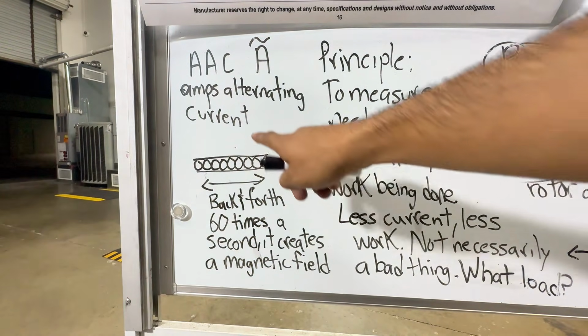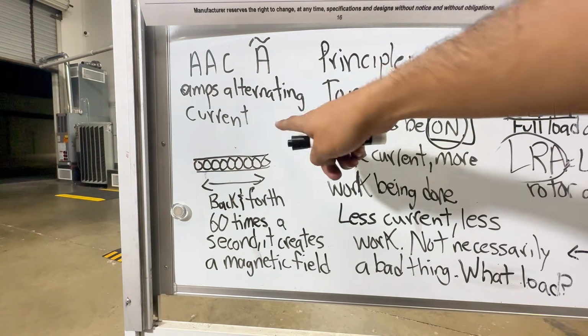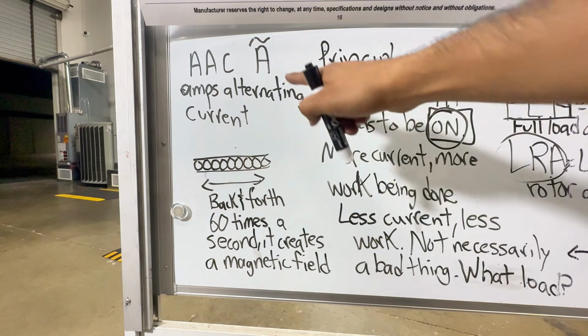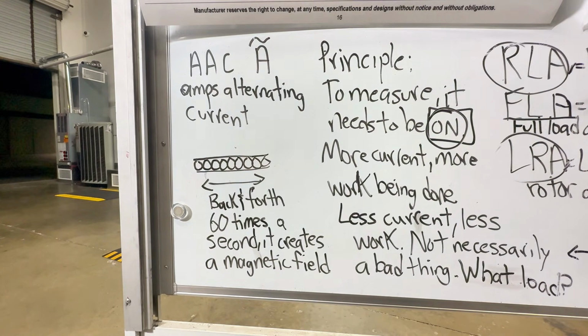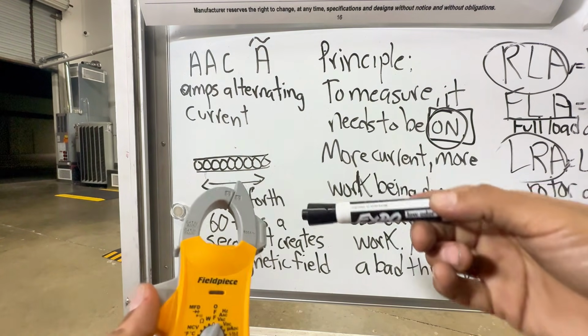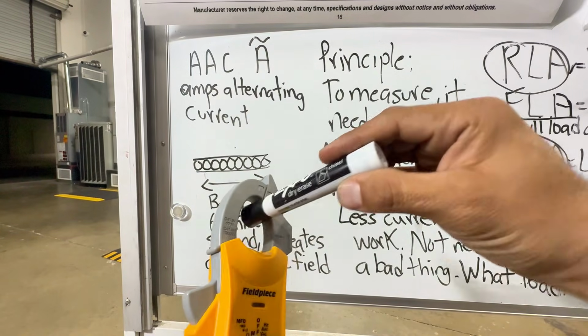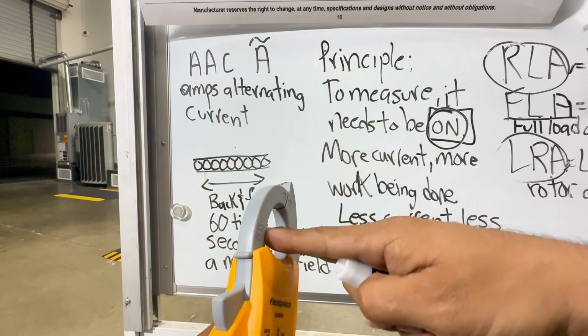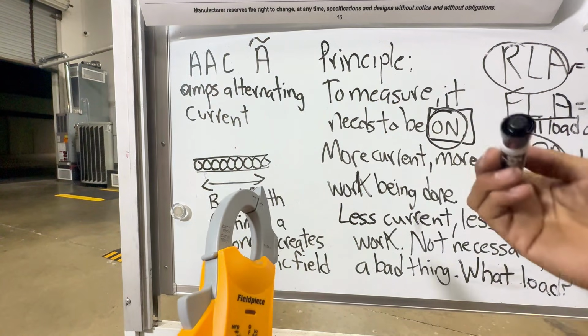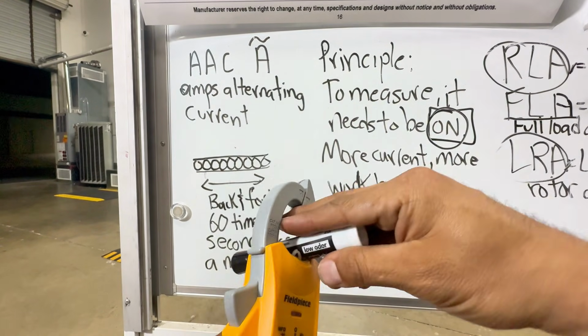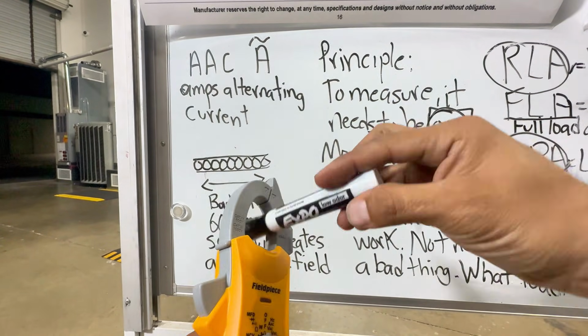But you're either going to see it like this, AAC, amps alternating current, or on your meter it might just say A with a little squiggly line. And the idea is that you're going to check amp draw on just one wire. You're not going to put two wires. You're going to put one wire, which I'll show you right now on the unit. But if you put two, it cancels out. You've got to put it around one.